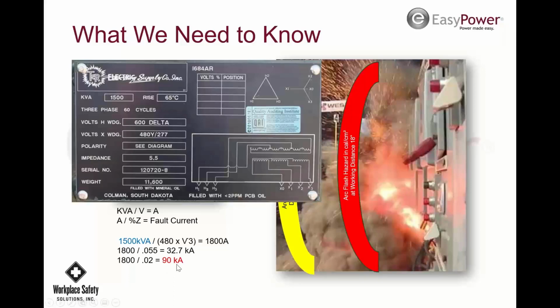Another thing to think about too, if you're working downstream from a transformer and you're protected by something on the other side of the transformer. So you're working on 208 volt stuff and there's no 208 volt disconnect after the transformer, there's only the 480 volt disconnect on the primary side of it. So whatever happens to you, the short circuit that occurs at the 208 side has to be protected by the fuse on the 480 volt side, and it's really hard to see that through that impedance of the transformer. And what happens usually is it'll burn itself clear before the fuse actually blows or the breaker trips.